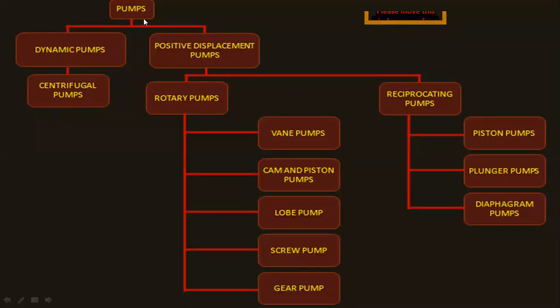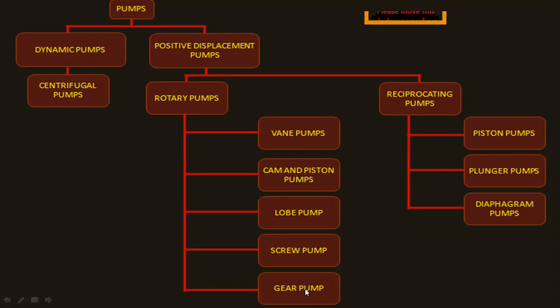Looking at the full classification: we have dynamic pumps, which form into centrifugal pumps, then positive displacement pumps with two main categories — rotary pumps and reciprocating pumps. Reciprocating pumps use piston, plunger, and diaphragm types. Rotary pumps are further classified into vane pumps, cam and piston pumps, lobe pumps, screw pumps, and gear pumps. In industry, centrifugal pumps are used in 90% of applications; piston and reciprocating pumps are used only in very specialized cases.